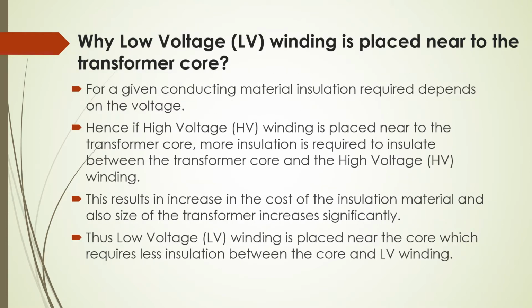Why is the low voltage winding placed near the transformer core? In the transformer, for a given conducting material, the insulation required depends on the voltage. Hence, if the high voltage winding is placed near the transformer core, more insulation is required to insulate between the transformer core and the high voltage winding. This results in an increase in the cost of insulation material, and the size of the transformer also increases significantly. Thus, the low voltage winding is placed near the core, which requires less insulation between the core and the LV winding.